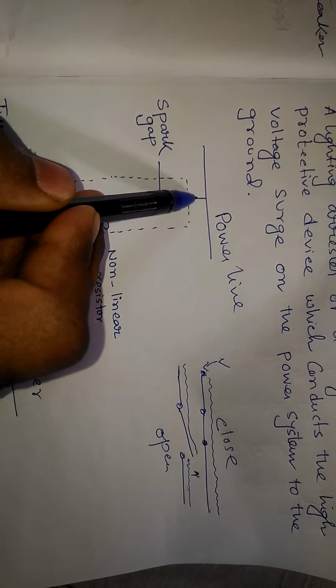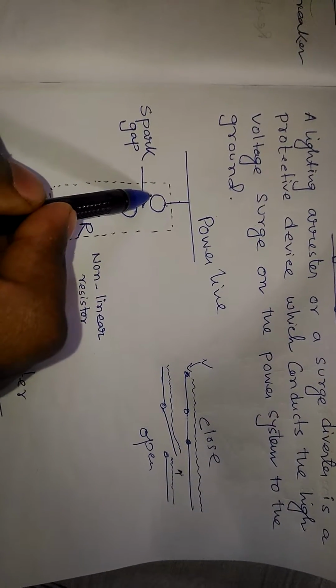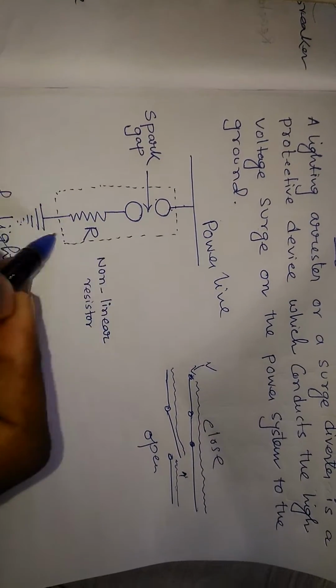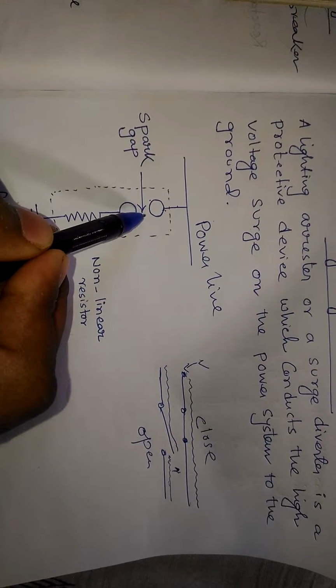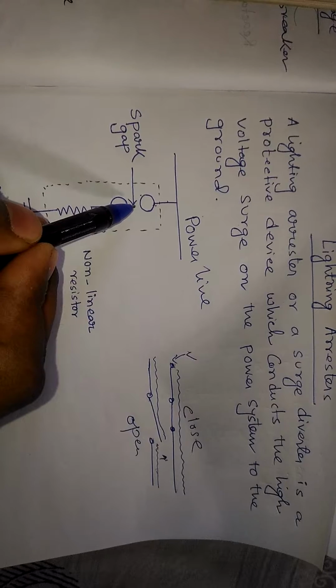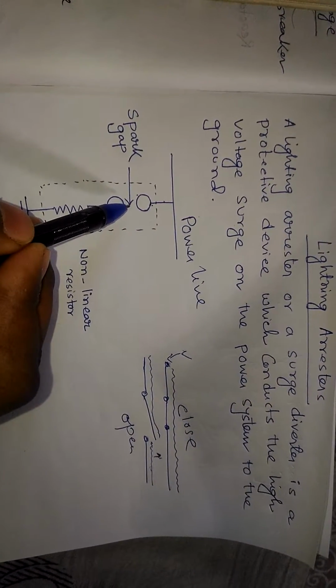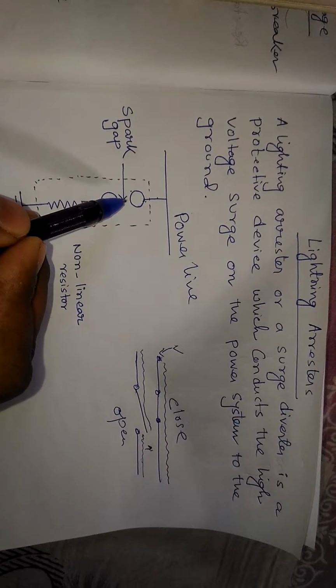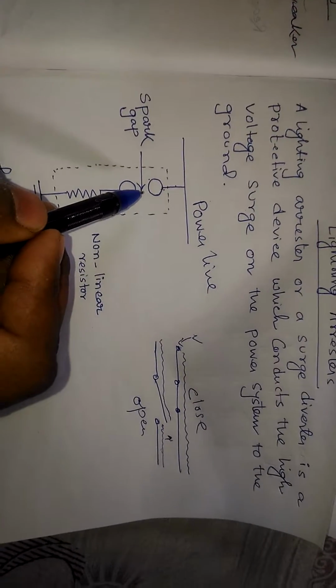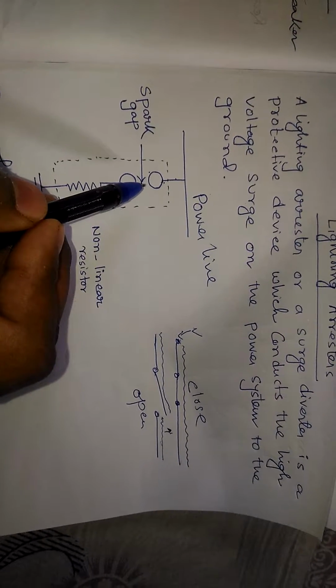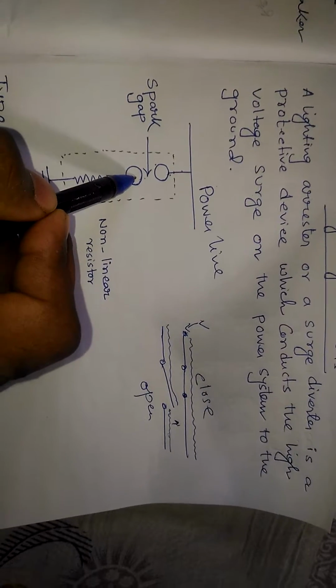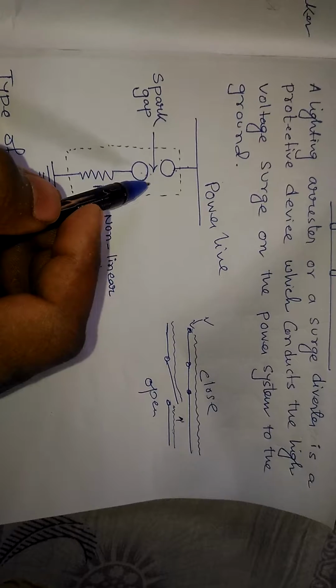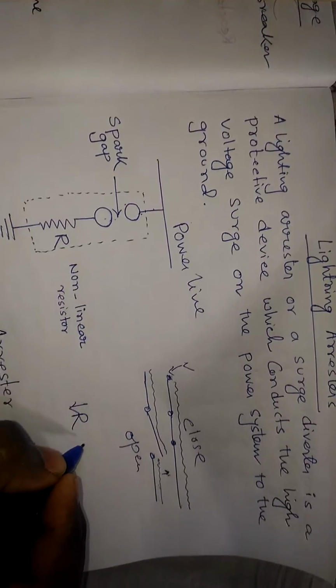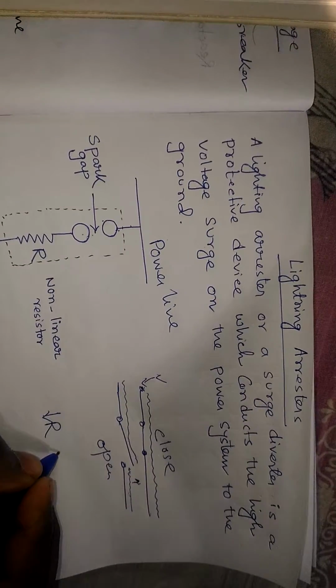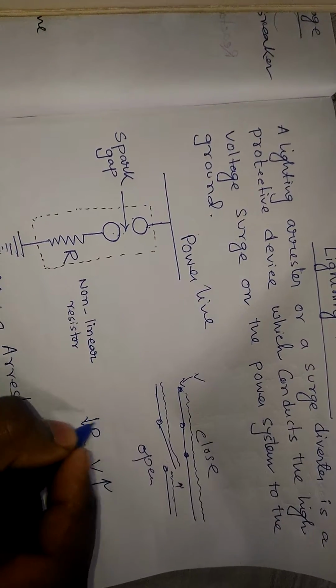One end of the lightning arrestor or diverter is connected to the terminal of the equipment to be protected, and the other end is effectively grounded. The length of the gap is so set that the normal line voltage is not enough to cause an arc across the gap, but a dangerously high voltage will break down the air insulation and form an arc. The property of a nonlinear resistor is that its resistance decreases as the voltage increases.